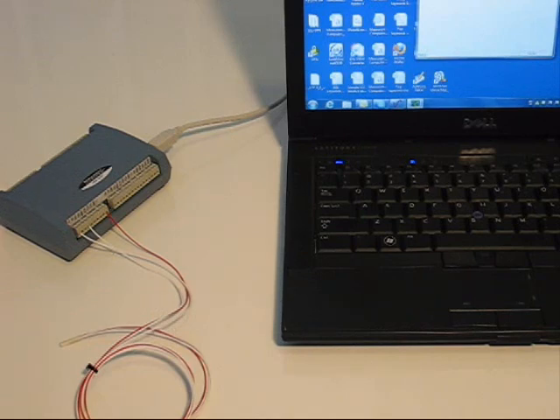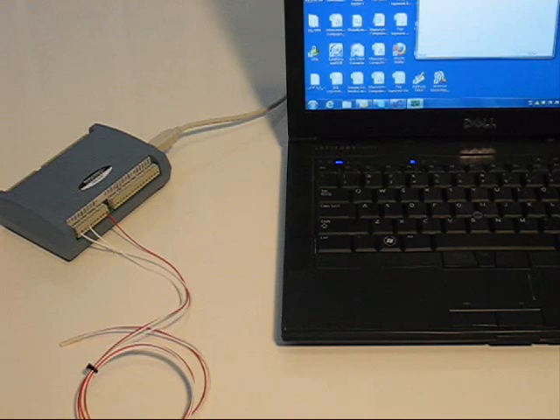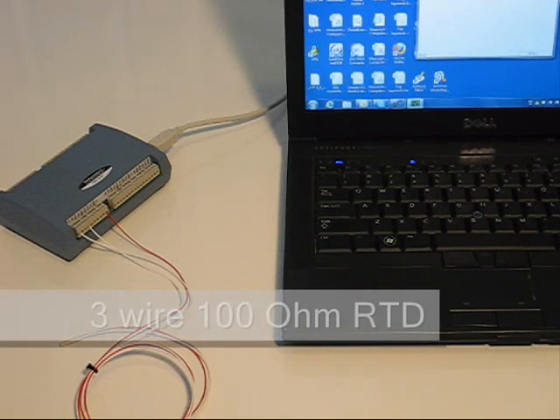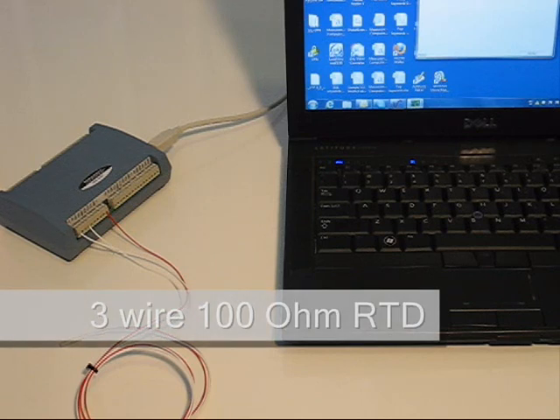Here we have a USB temp connected to a laptop with an RTD connected to channel 1. In this video we're using a three-wire 100 ohm RTD.